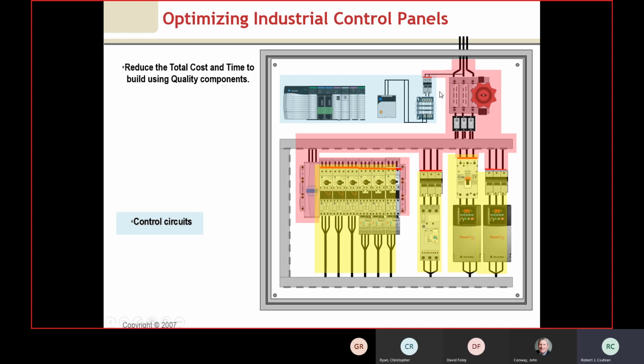Notice typically we're going to do some type of methodology here. In this case, we've tapped off the power side so that we can keep the controller going even when the main disconnect is shut off, so we can do some troubleshooting, programming, or updating of this unit with power removed from the device. And then we will supply power, maybe through a transformer or a power supply, to get to the control unit.